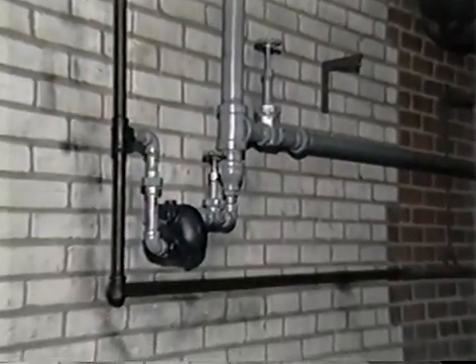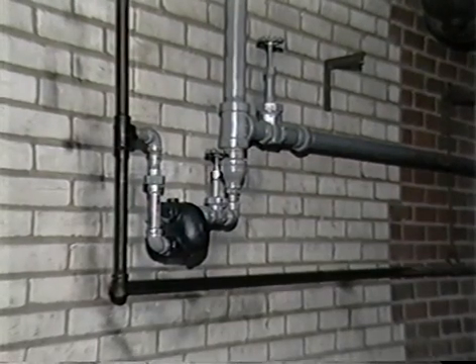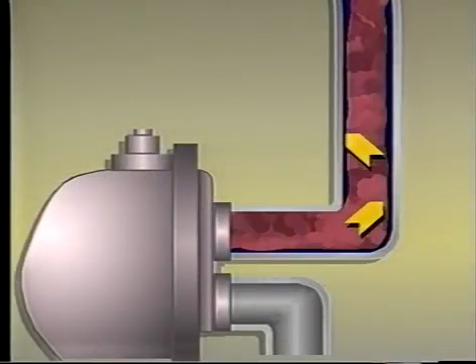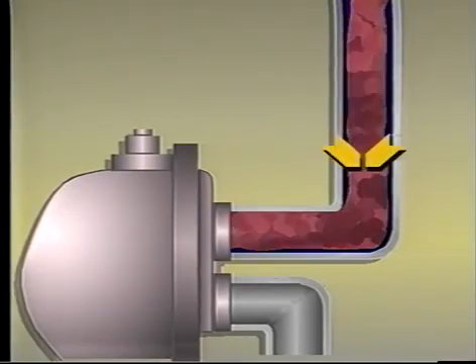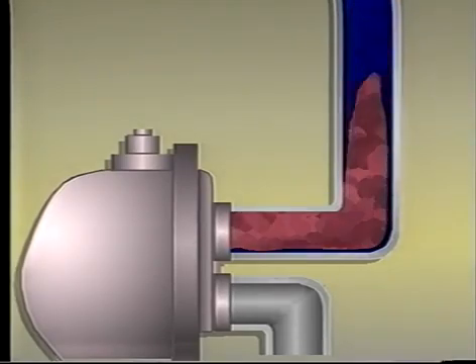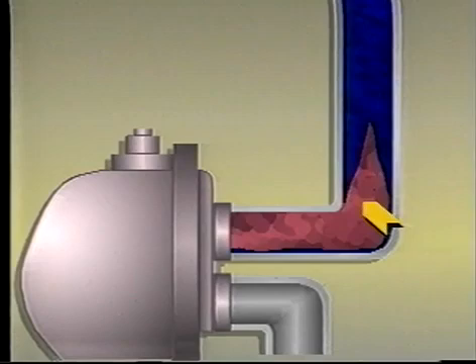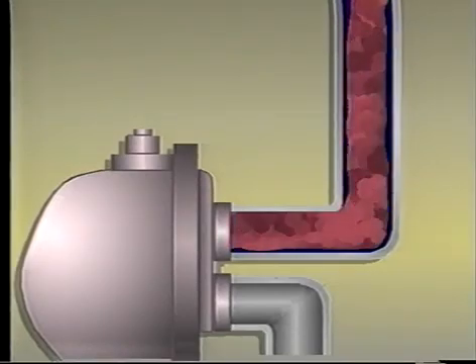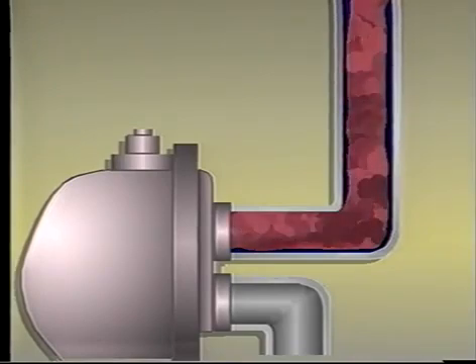Differential shock can also become a problem when elevated heat exchange equipment is drained with a substantial vertical drop ahead of the trap. Under normal conditions, condensate drains down the walls of the pipe. A sufficient volume of steam constantly flows down the center of the pipe to replace the steam that is condensed by radiation losses of the piping and the trap body itself. The steam flow rate increases if a thermostatic element such as the bellows or wafer in an F&T trap opens. If a slug of condensate seals off the pipe, steam collapses downstream of the seal. Again, a pressure differential forms and this, along with gravity, accelerates the slug. When this piston strikes the trap, it can damage a float, the thermostatic element, or other parts of its mechanisms.